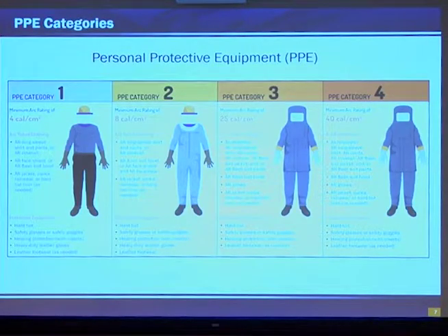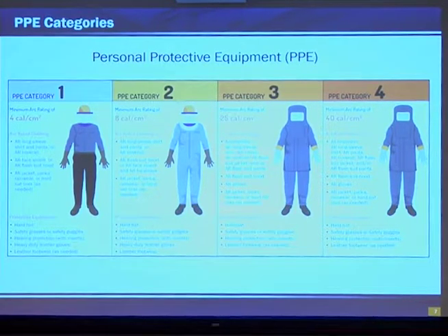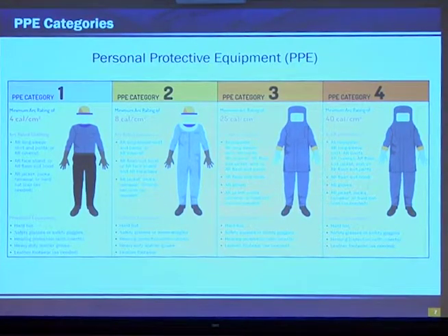PPE categories. Wearing the proper personal protective equipment will protect workers from the hazards of an arc flash. The 2015 NFPA 70E recognizes 4 different categories of PPE. Each category has a different arc rating it can protect you from. Looking at our fancy picture, these ranges begin at 4 calories per centimeter squared to 40 calories per centimeter squared. Now I want to note that these are the high end of the incident energies.